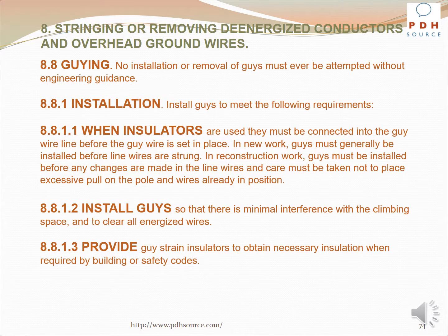No installation or removal of guys must ever be attempted without engineering guidance. Install guys to meet the following requirements. When insulators are used, they must be connected into the guy wire line before the guy wire is set in place. In new work, guys must generally be installed before line wires are strung. In reconstruction work, guys must be installed before any changes are made in the line wires, and care must be taken not to place excessive pull on the pole and wires already in position. Install guys so that there is minimal interference with the climbing space and to clear all energized wires. Provide guy strain insulators to obtain necessary insulation when required by building or safety codes.